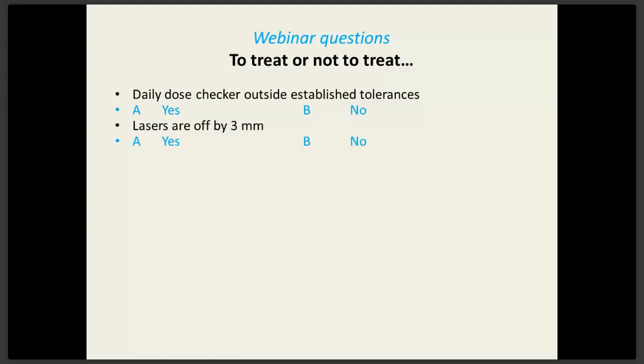Table shifts. In the morning, you're testing your table shifts and they're off by 5 millimeters on a test cube. What to do? Yes or no? All right, this one is also up in the polls, so go ahead and put your answer in, and we'll go over the correct one in just a moment. Let me jump in, just in the interest of time. Table shifts off by 5 millimeters. I would not treat until, again, you had confirmation by the physicist, because a 5 millimeter shift remotely, where you can't even see what's going on after you've imaged the patient, is pretty significant. This is a controlled shift on a cube. If it's off by 5 millimeters, something is wrong in the analyzing software or in the actual table mechanism.